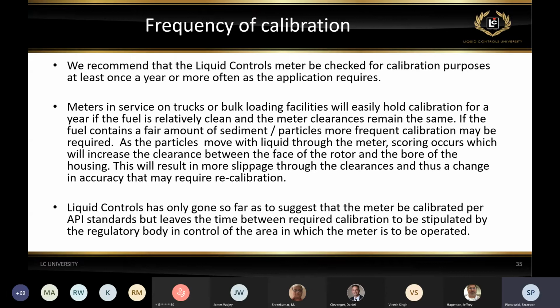Generally speaking, our meters will hold the calibration for a year as long as the product is fairly clean. If the product is not very clean, the sediments or debris in the product will move through the meter with the liquid, causing erosion of the surfaces of the meter. As a result, you will see increased clearances inside the meter, between the rotors and the housing and the bearings, and you're going to see increased slippage of product through the meter. Increased slippage will create inaccuracy and call for recalibration. So really, we don't tell how often, we just recommend once a year.